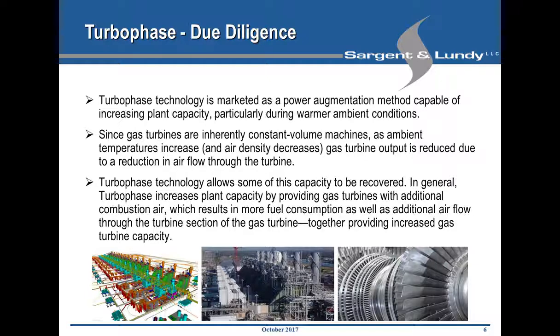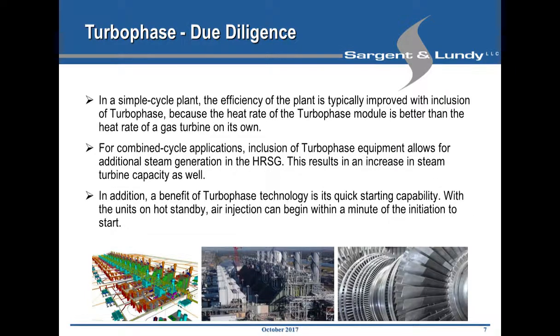Now, as Steve has very well explained, Turbophase is a power augmentation method, and clearly has a huge advantage in regards to warmer ambient conditions, where all gas turbines, as constant volume machines, show a reduction in power output that can be up to 5 to 10%. Clearly, this is the opportunity where the Turbophase technology allows some of this reduced capacity to be recovered. If we go to the next slide, as Sargent Lundy, we have confirmed that the inclusion of Turbophase will result in a better heat rate in simple cycle.